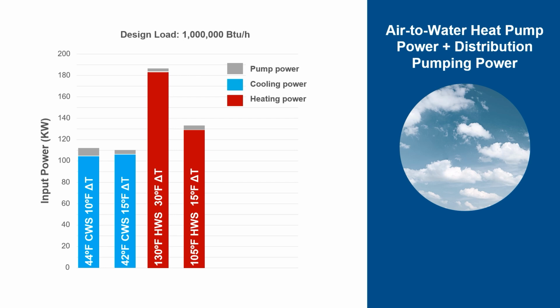As shown in gray, there is a significant increase in pump power with a 105-degree supply and a 15-degree delta T. But the combined heat pump plus pumping power is still 30% less than the system designed for a 130-degree supply and a 30-degree delta T. That's an additional 54 kilowatts for a 1,000,000 BTU per hour. At part load, these savings continue. The far right bars depict 25% of the design heating load at 35-degree ambient.